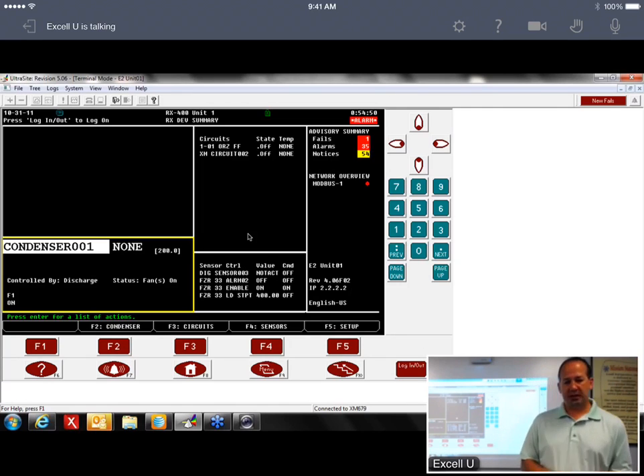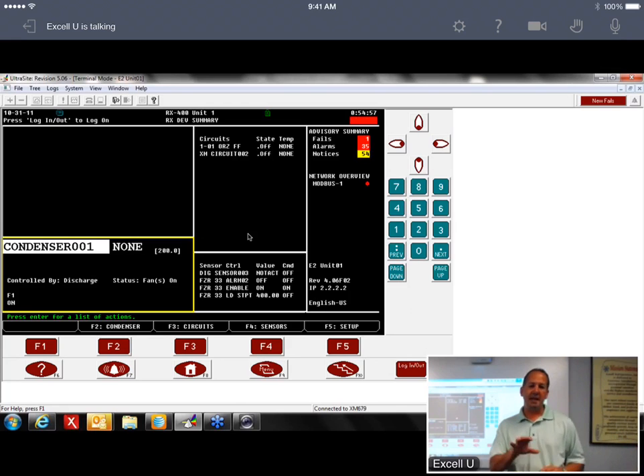So what it does: the XM device has, I think, 299 parameters in it. With the E2, we tried to keep it the same as we did for CCB and CC100. So you actually have your XM device, which is a network piece, and then you have your XM circuit. The XM circuit has all of your set points, your defrost settings, all that type of stuff. Those two combined, the device and the circuit, create those 299 parameters that reside in there.